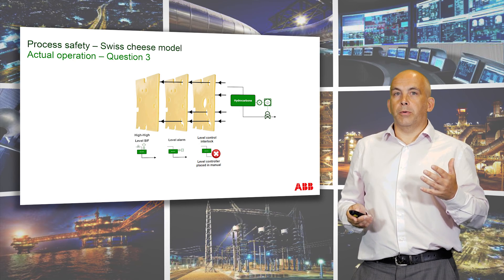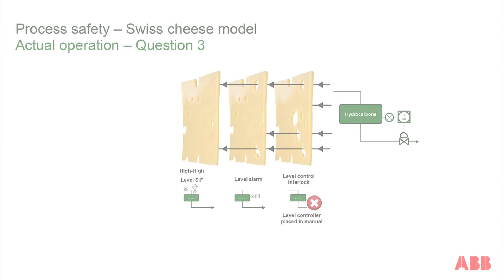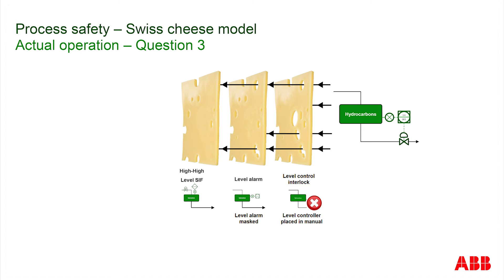It becomes annoying for the operator. So the operator thinks he'll mask that alarm until the level control gets resolved. As soon as the operator masks that alarm, we've made the second barrier ineffective — introducing another hole in that particular slice of cheese.